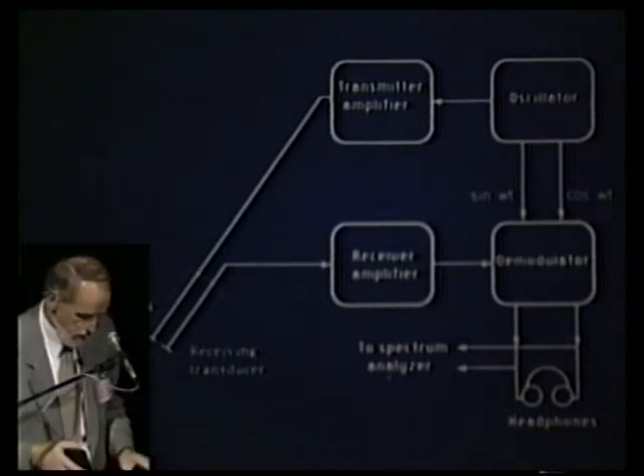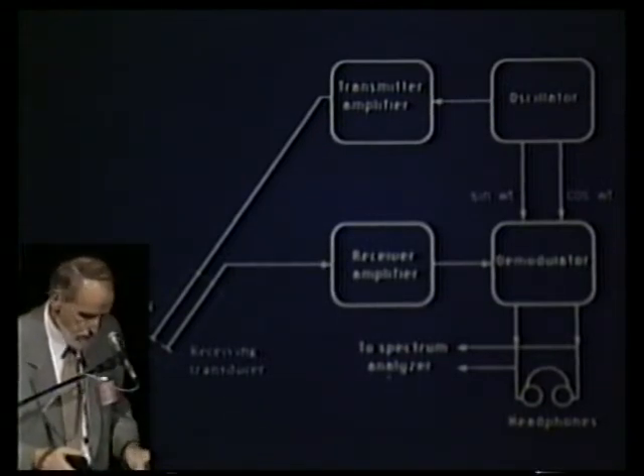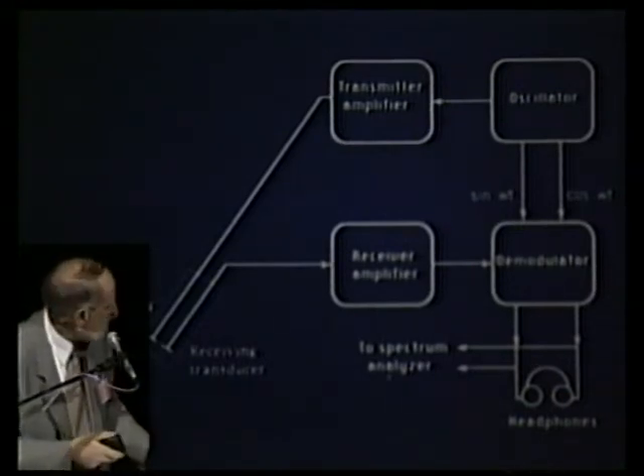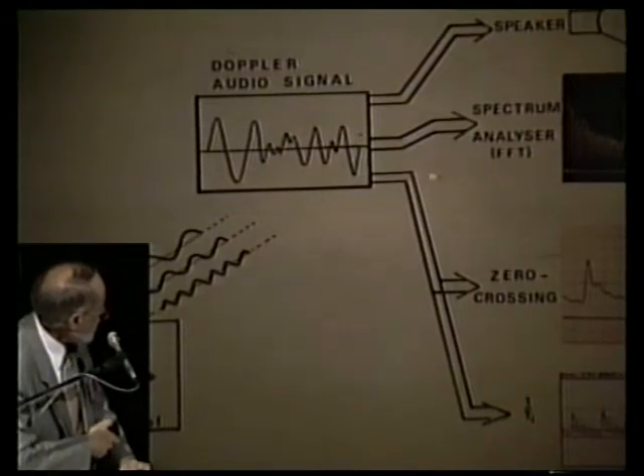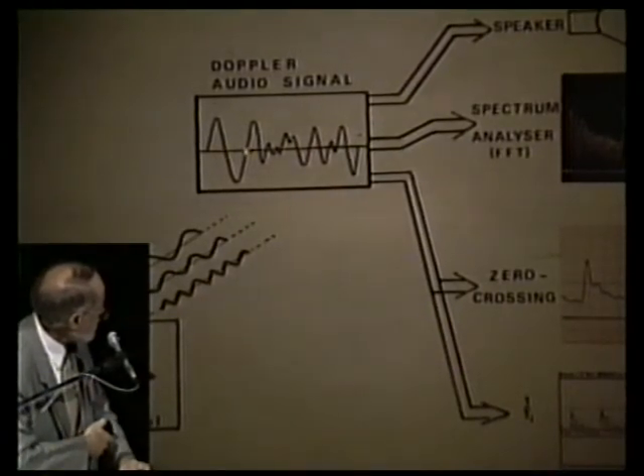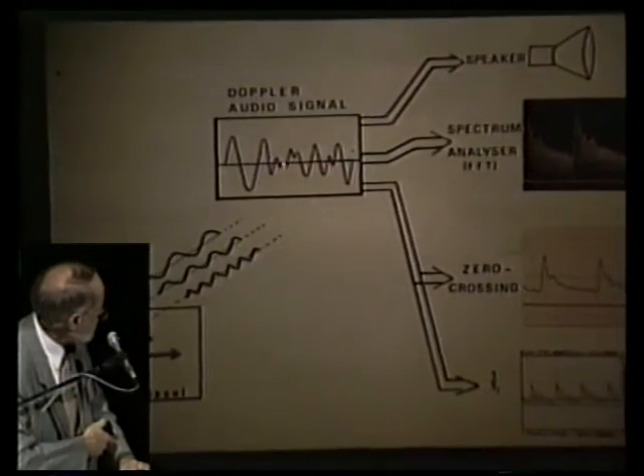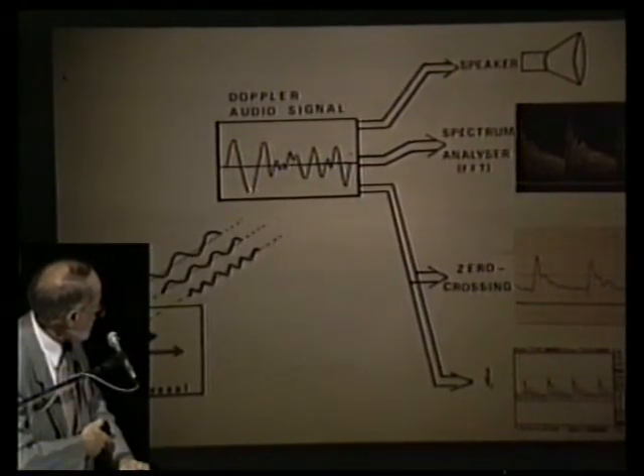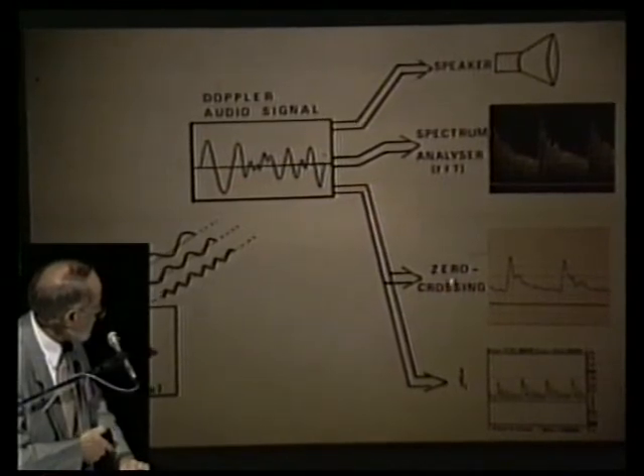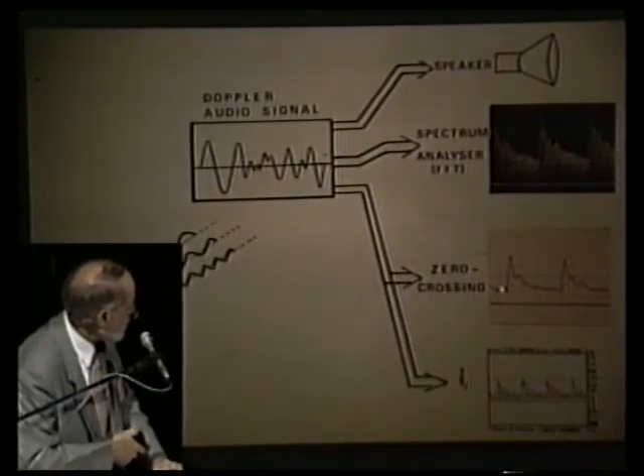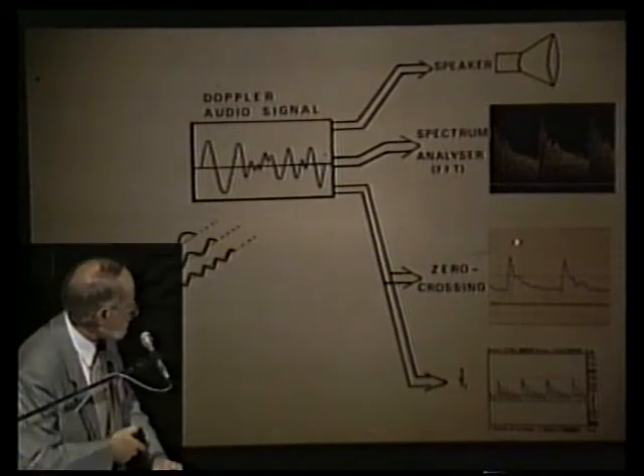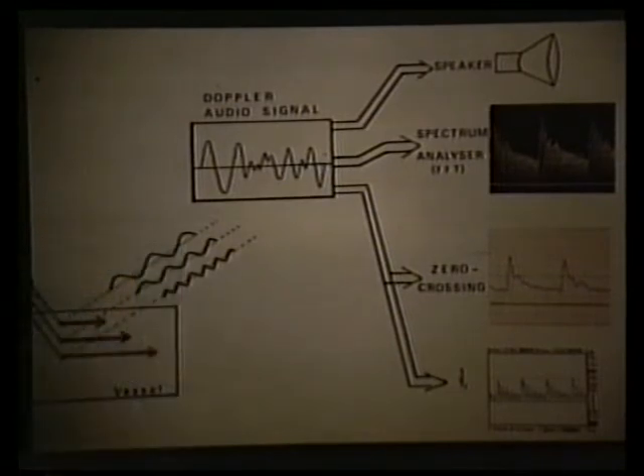In the demodulator, the velocity signal corresponding to the positive or negative Doppler shift can be sent to a spectrum analyzer, a loudspeaker, or sometimes a zero crossing detector. A zero crossing detector measures the time between each zero value of the Doppler signal, providing information related to the mean frequency. This velocity curve can then be registered on a strip chart recorder.